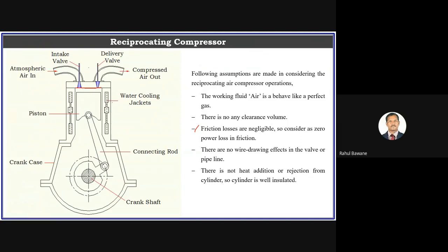The next assumption is that there is no wire drawing effect in the valve or pipeline. The wire drawing effect is always there. During suction, the intake passage volume is more than the valve opening, so all that volume is drawn through this small opening of the valve. During delivery also, the volume inside the cylinder is more than the small delivery valve opening it is delivered through. So there is a wire drawing effect, but it is assumed to be absent.